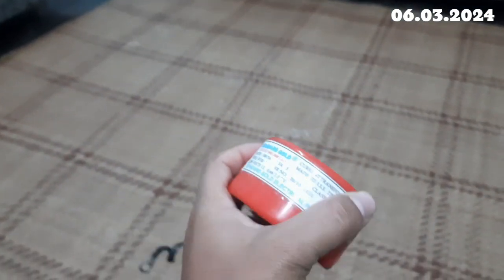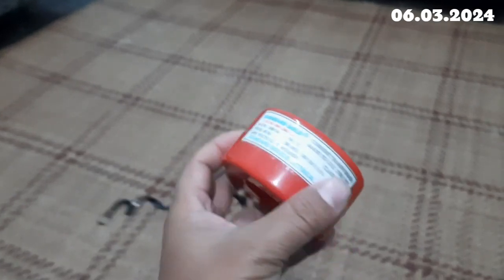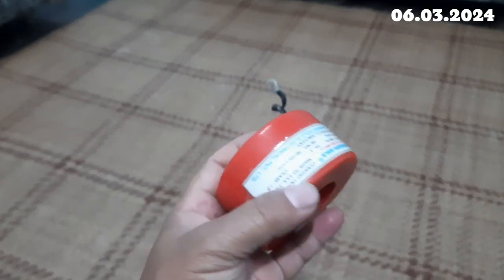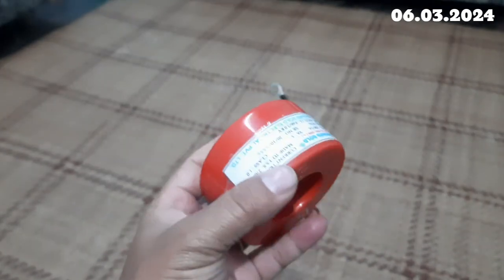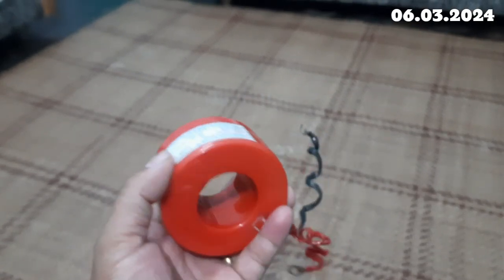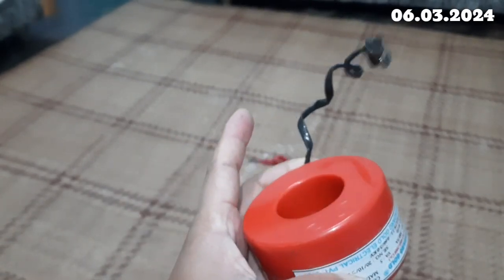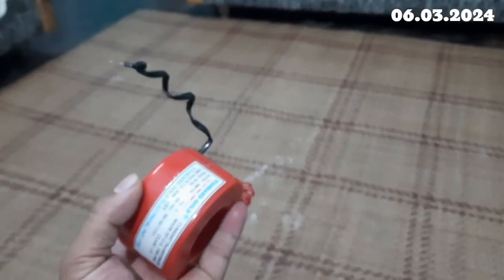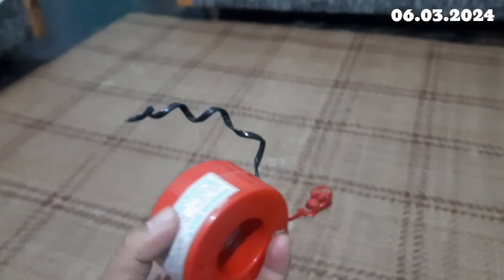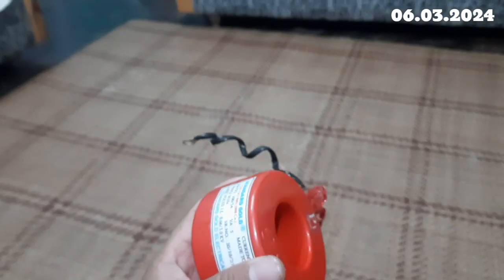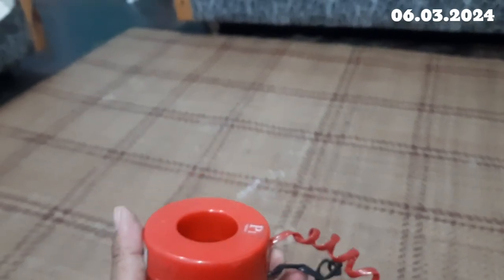I don't have the 150/5 with me, but we have different ones depending on the current that you calculate using this formula, 3-phase power P = √3 VL IL. Since most of the time we are dealing with LT metering, P will be your connected load or your demand, whatever is the case. √3 is just a factor, VL is the line voltage, you can take 415, and IL is what is to be calculated.